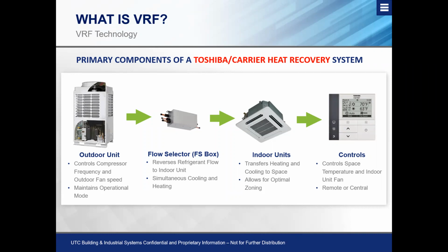Now, this is where I want to get into talking about calling the system a 2-pipe versus a 3-pipe system. That would be correct on the heat recovery side of things because, again, that's where the separation process takes place, or how you label those. But both of these systems have a heat pump option, as I stated before, which is just a strict heat pump option. We're not going to have a flow selector. We're going to have an outdoor unit, an indoor unit, and some form of control, which means this system that is commonly referred to as a 3-pipe on the heat recovery side of things is actually now a 2-pipe system.